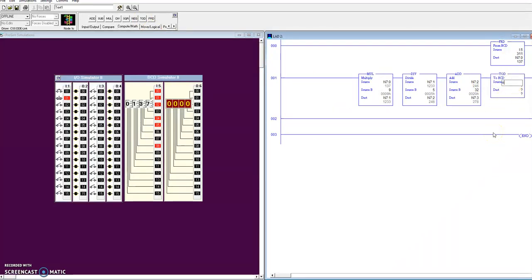So we're going to take our result, convert that to BCD, and put it in output register 6. That's going to give me some crazy number, what it looks like over here. It looks like it's putting in 632, but the BCD converted version of that is 278. 278 is what I should be seeing.